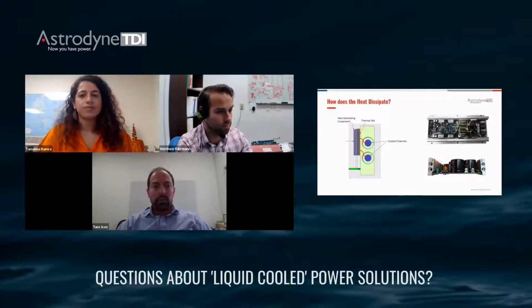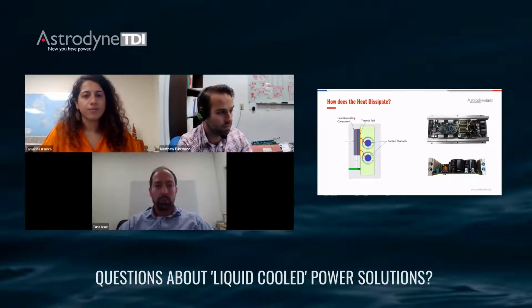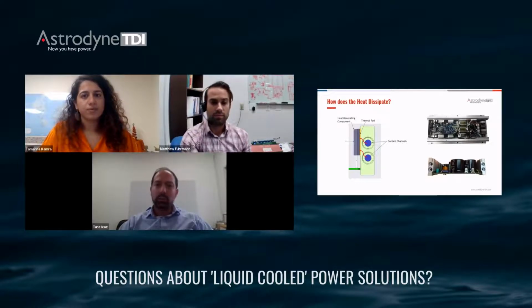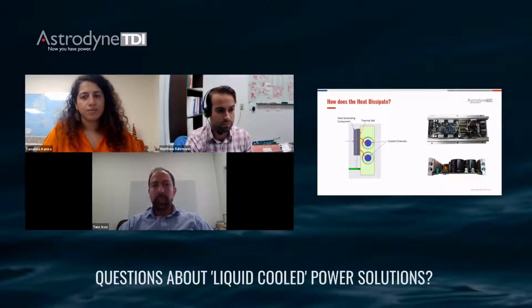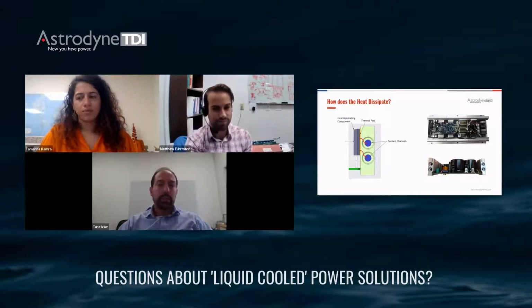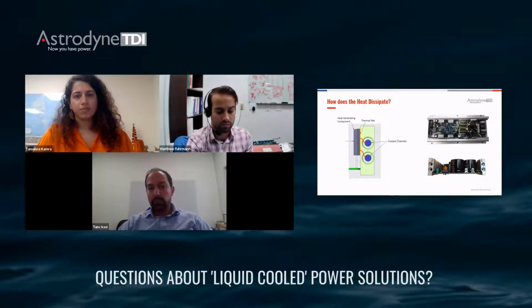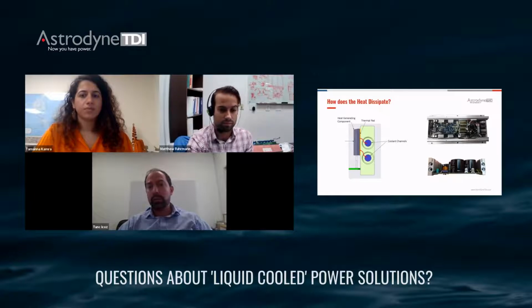Let's start at the component level. Typically, in a typical application, the heat-generating power devices are mounted on heat sinks, cold plates, or heat exchangers, usually with a thermal interface material between them to reduce contact resistance and provide a better conduction path. The heat generated by these devices raises the heat sink temperature, illustrated as the green block in our cartoon sketch. As the heat sink temperature goes up and water starts flowing through the cooling channels, the water picks up heat from the metal, and with the proper flow rate transports it to a remote location where this heat is rejected, either to outside air through a radiator or to another liquid media by a chiller.